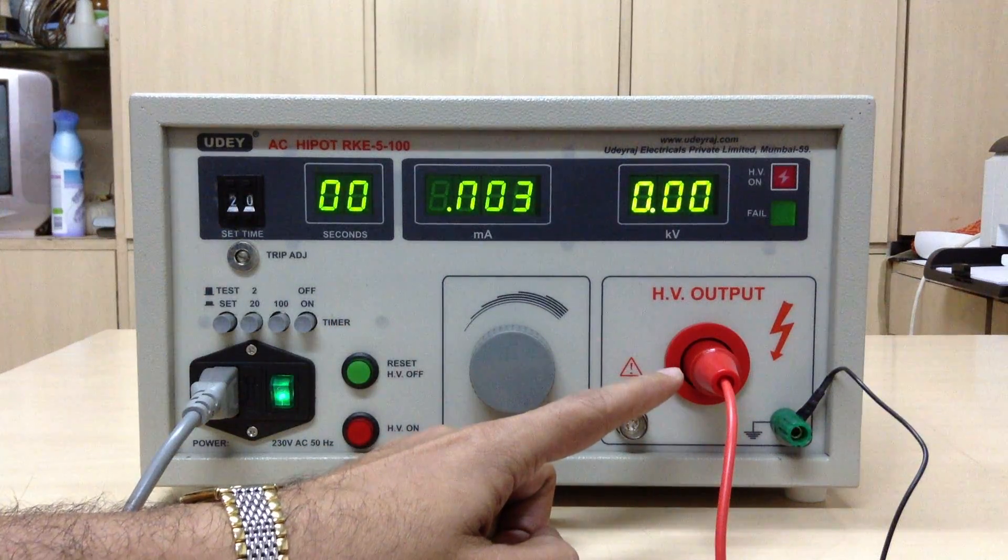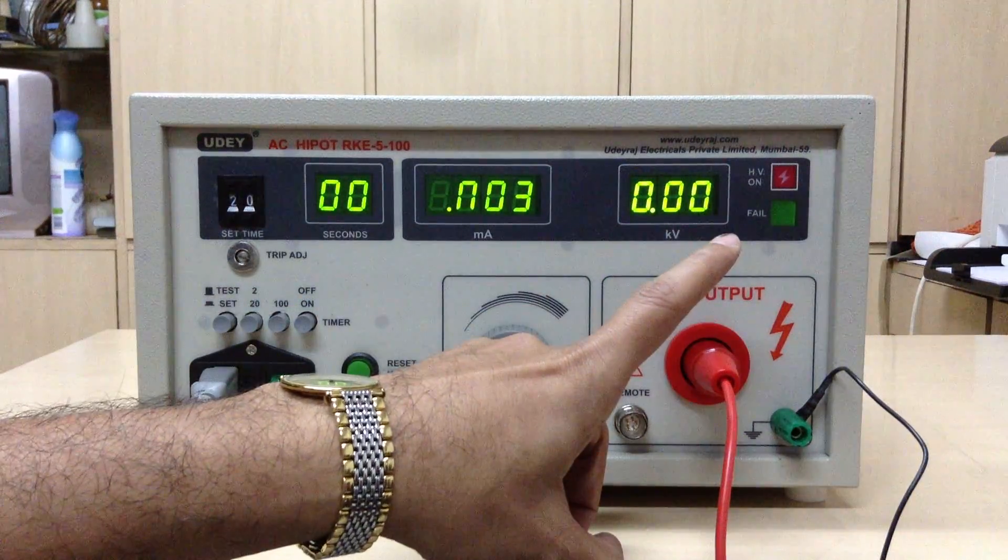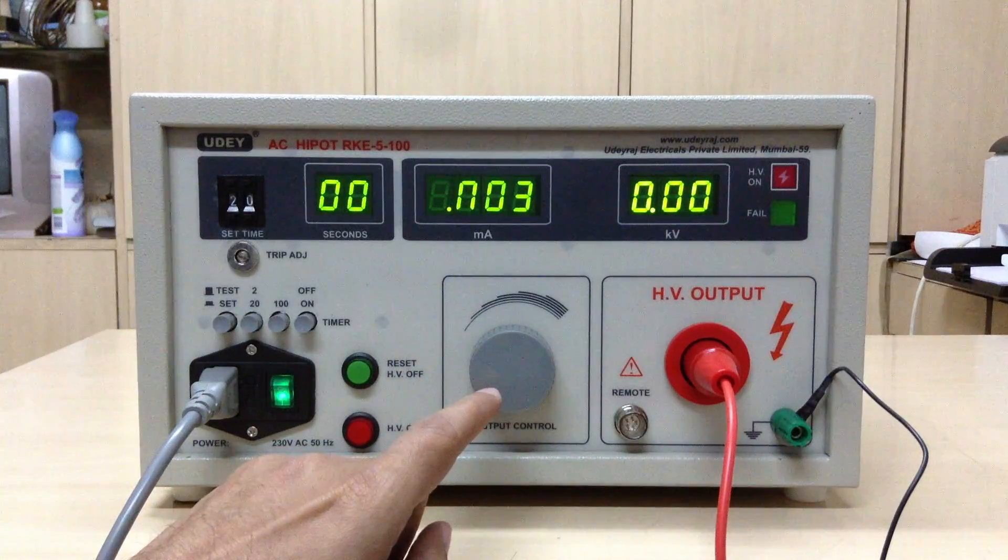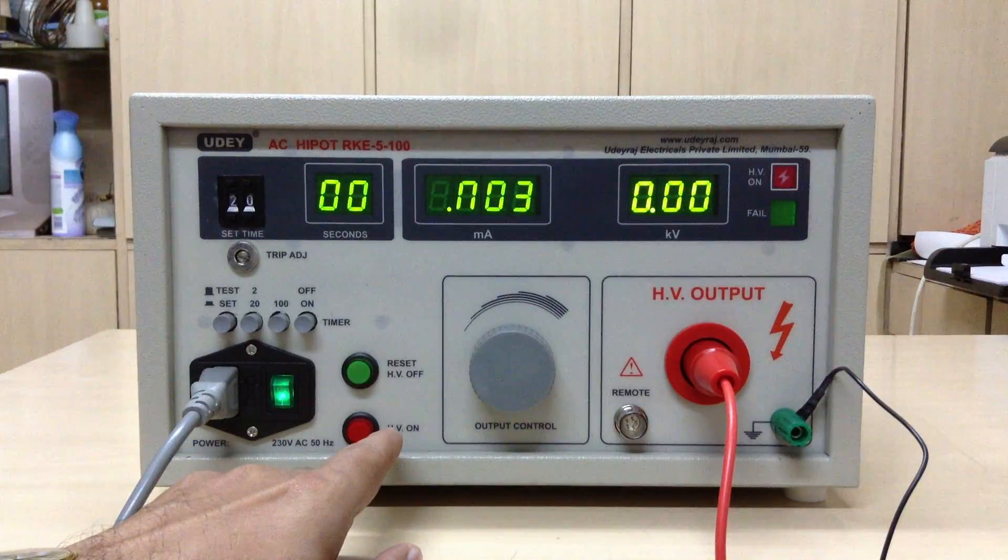The HV output is connected here, the earthing is connected here, and the HV ON indication is seen there. Failure indication is seen there. This is an output control, this is a reset HV OFF, HV ON push button switch.